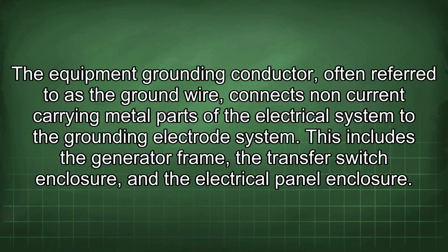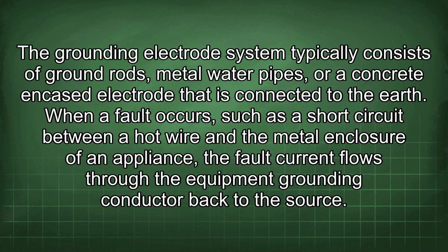The equipment grounding conductor, often referred to as the ground wire, connects non-current carrying metal parts of the electrical system to the grounding electrode system. This includes the generator frame, the transfer switch enclosure, and the electrical panel enclosure. The grounding electrode system typically consists of ground rods, metal water pipes, or a concrete encased electrode that is connected to the earth.